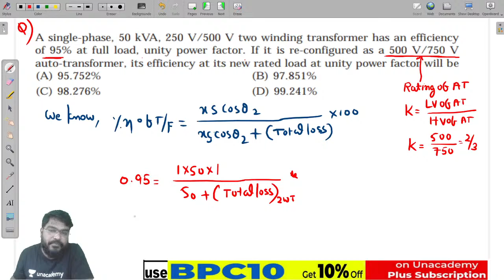We don't know the total loss, so we have to calculate the total loss of the two winding transformer. No need to multiply here, already I have taken 0.95. So now the total loss of the two winding transformer is equal to 50 divided by 0.95 minus 50. Now calculate this. 2.631 kilowatts, right? Okay, it is the total loss of the two winding transformer.